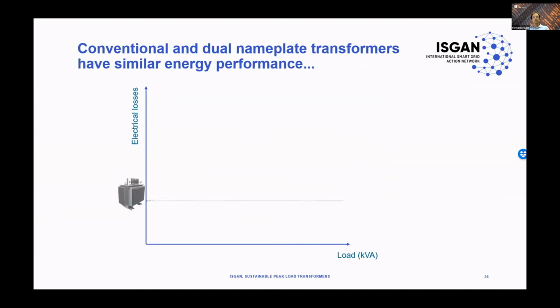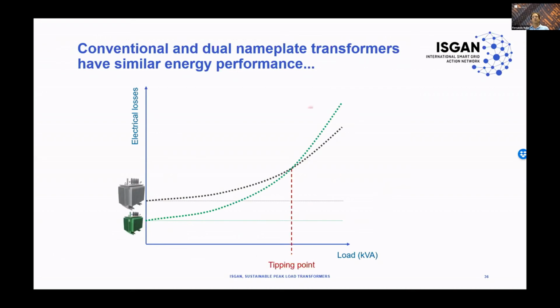So how do these compare? We represent here the no-load losses and the winding losses of a conventional unit. Then we represent the sustainable peak load unit, which is smaller, so the core losses are lower and the winding losses are higher. And then there is a point where the loss is equal. So the issue with these technologies is to know whether we are behind or beyond this tipping point in terms of loading, more notably in terms of average loading.